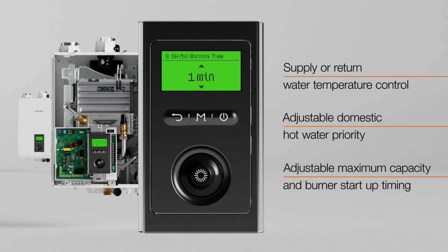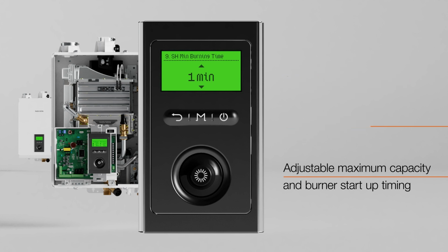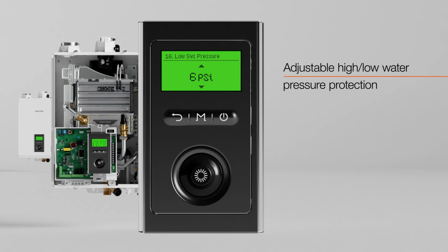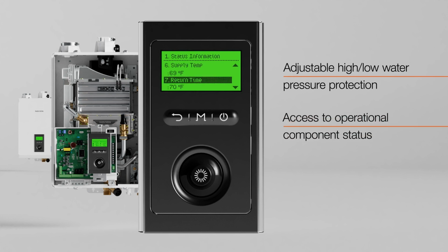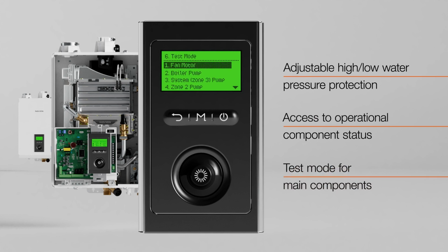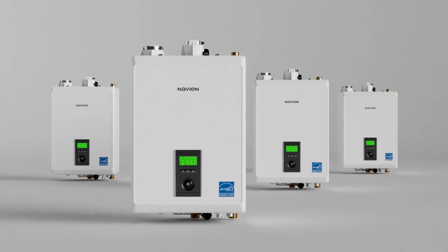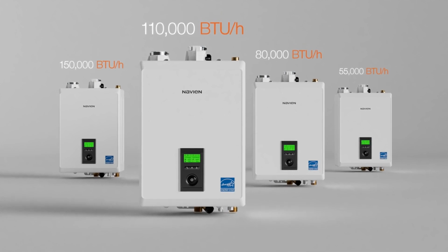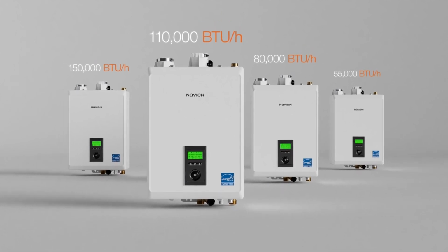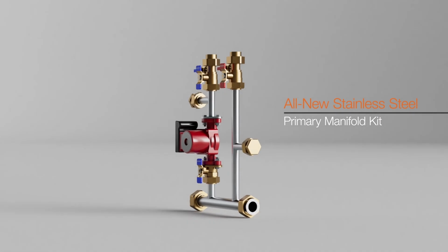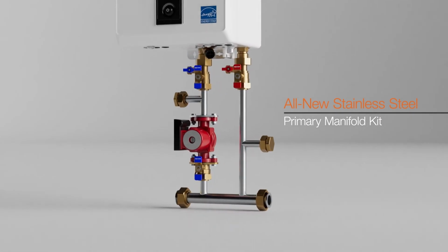Easily match system requirements with adjustable maximum capacity and burner startup timing, along with high and low water pressure settings. Access to operational component status allows users to monitor and maintain the boiler's performance, while a test mode for main components facilitates easy diagnostics and troubleshooting to streamline maintenance procedures. This series of condensing heating boilers is available in 4 sizes: 55,000, 80,000, 110,000, and 150,000 BTUs per hour. For easier installation and consistent performance, an all-new, system-matched, corrosion-resistant stainless steel primary manifold kit is available for each model.